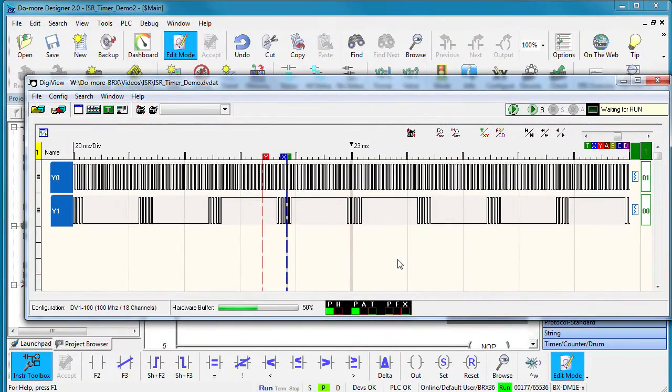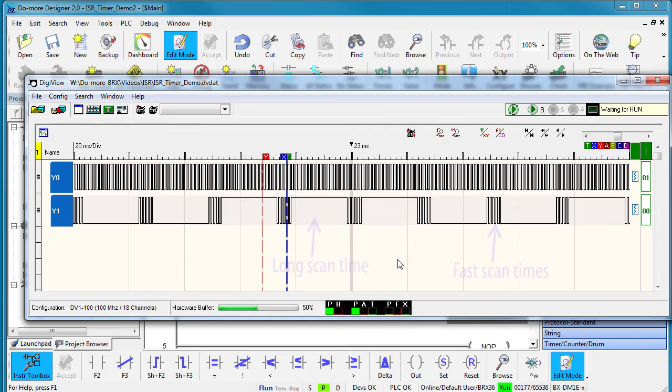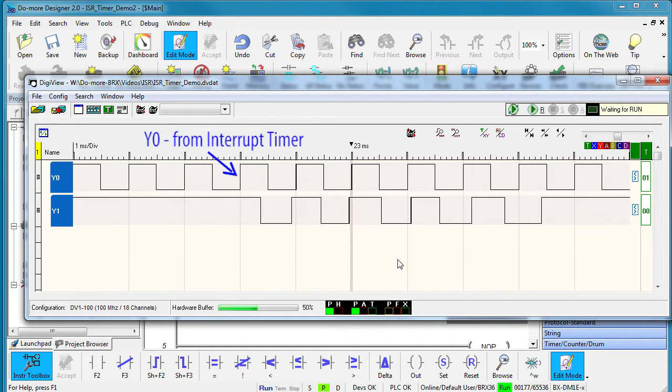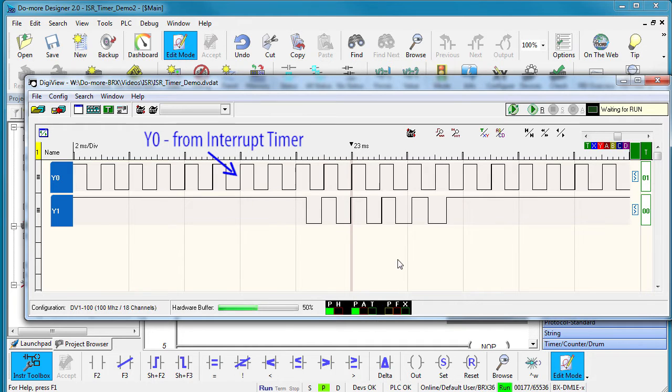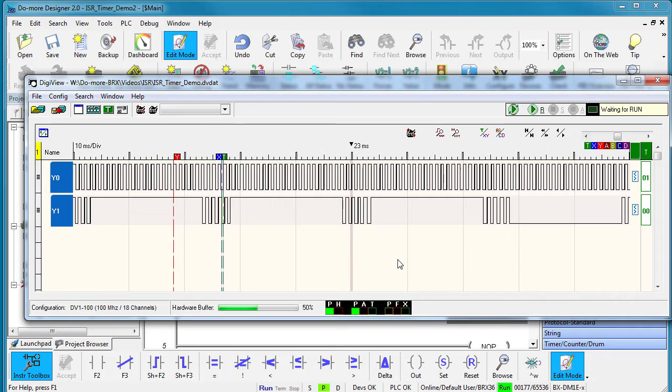Now if we look at those outputs on the logic analyzer, we can see that Y1 toggles every scan and some scans take a lot longer than others when that task gets enabled. But Y0, which is toggled by the interrupt timer event, toggles at regular intervals completely independent of the scan time. Again, exactly what we expect.